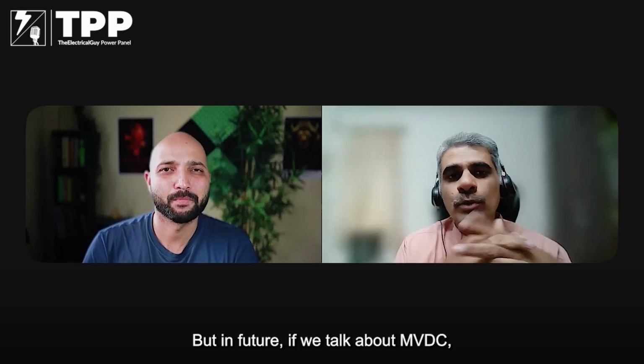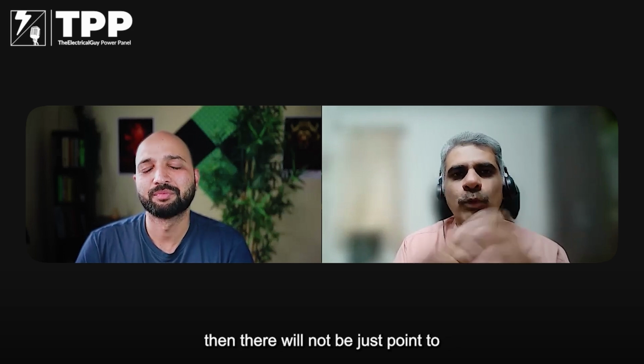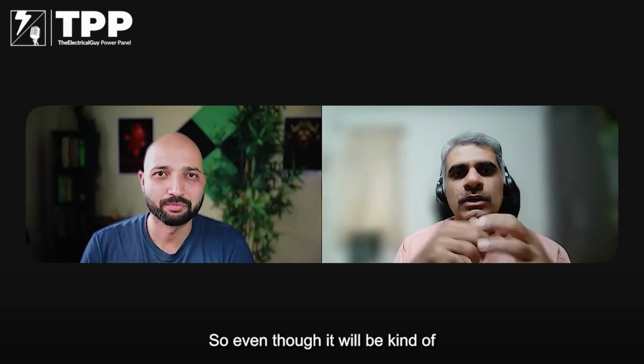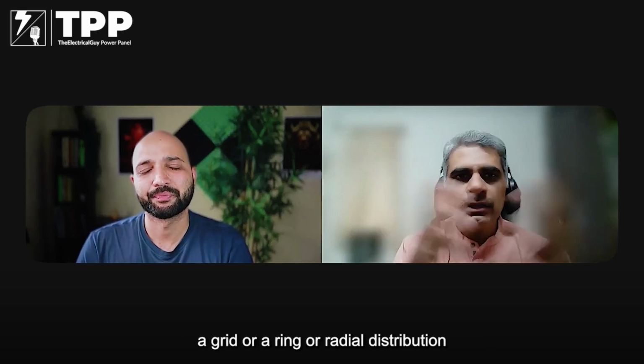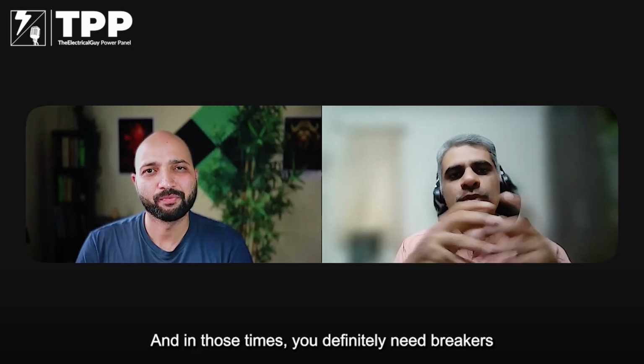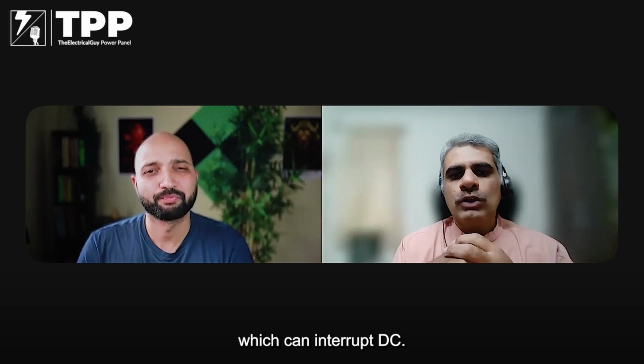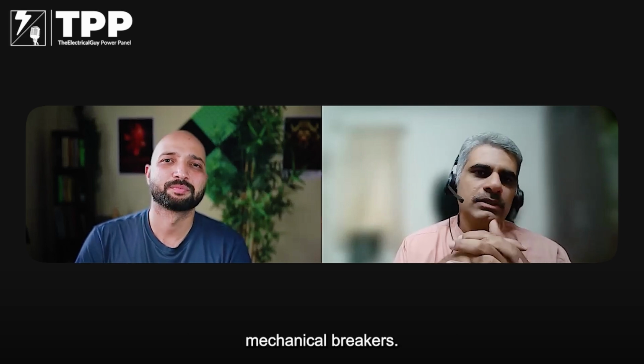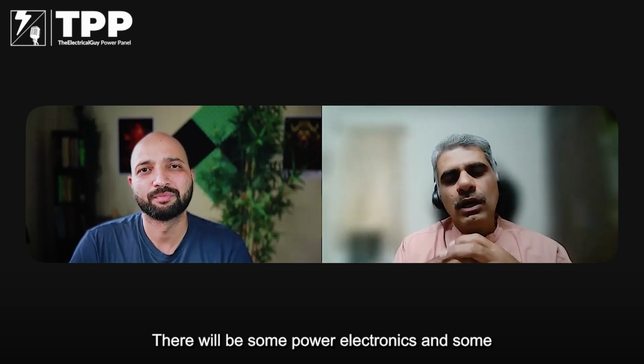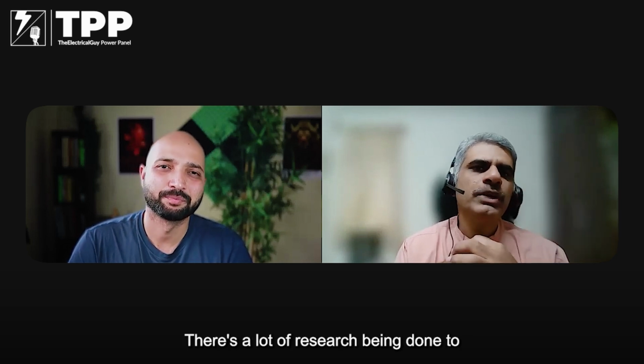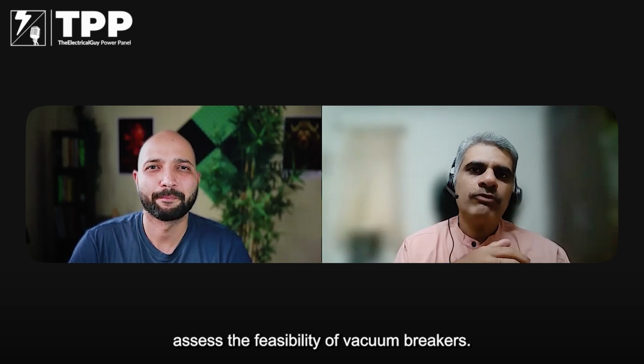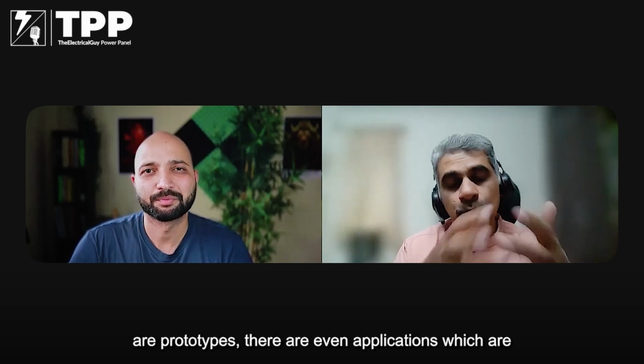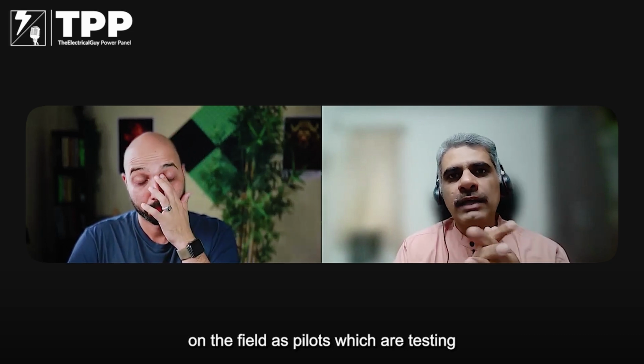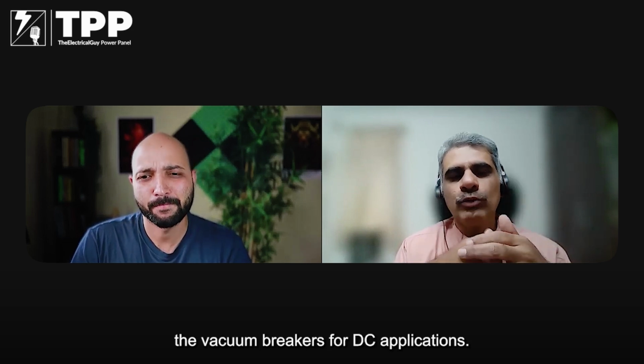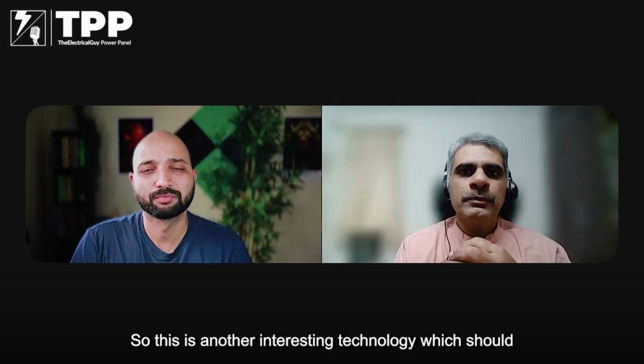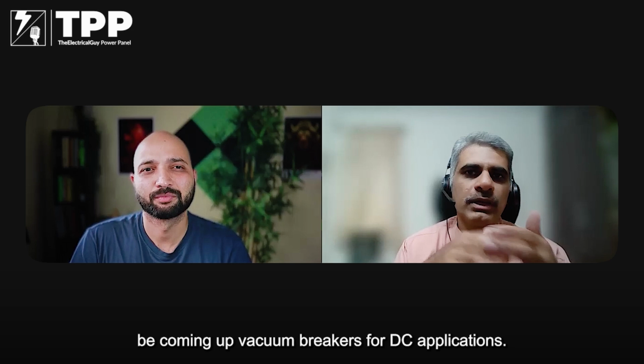But in future, if we talk about MVDC, then there will not be just point-to-point lines. There will be multi-terminal networks. It will be kind of a grid, or a ring or a radial distribution may happen in future. And in those times, you would definitely need breakers which can interrupt DC. DC breakers will not be completely mechanical breakers. As I understand, they'll be hybrid. There will be some power electronics and some mechanical devices like vacuum breakers. There's a lot of research being done to assess the feasibility of vacuum breakers. There are prototypes, and there are even applications in the field as pilots, which are testing vacuum breakers for DC applications. So this is another interesting technology which will be coming up: vacuum breakers for DC applications.